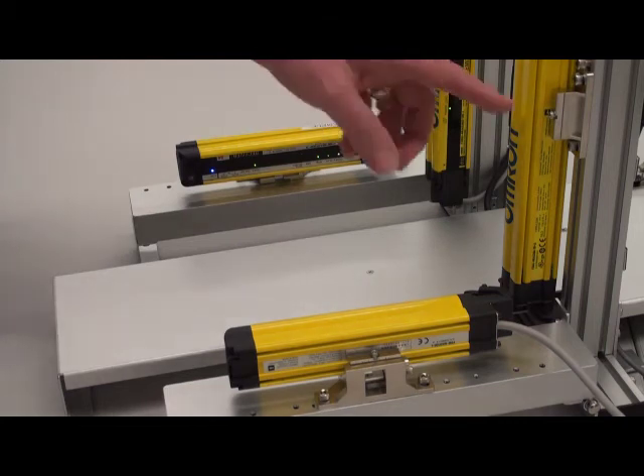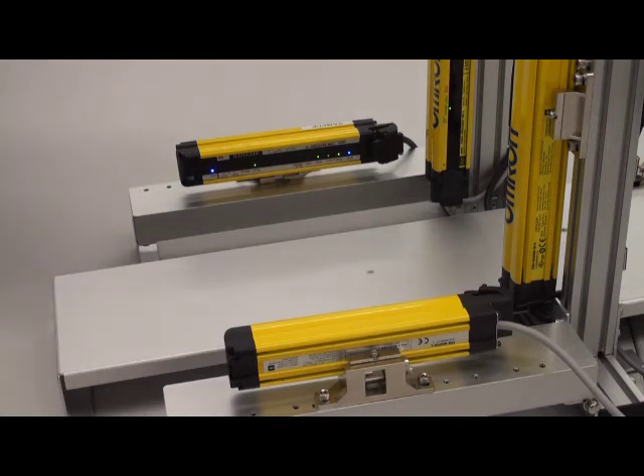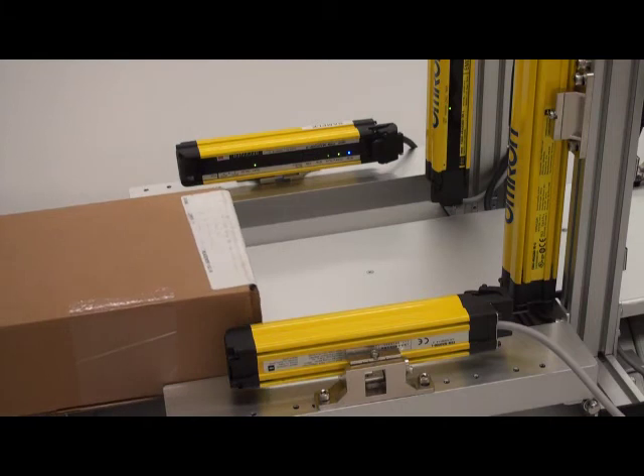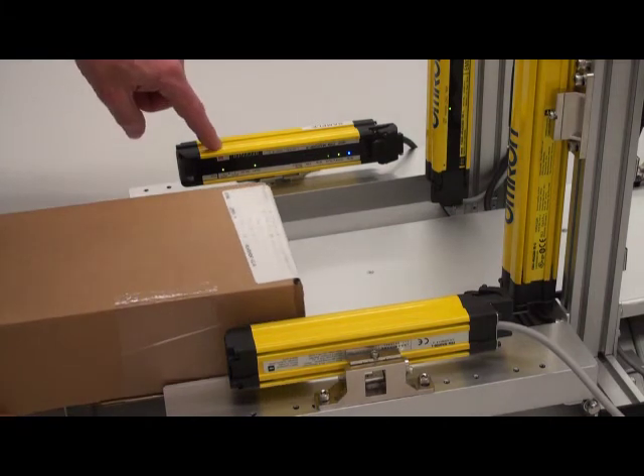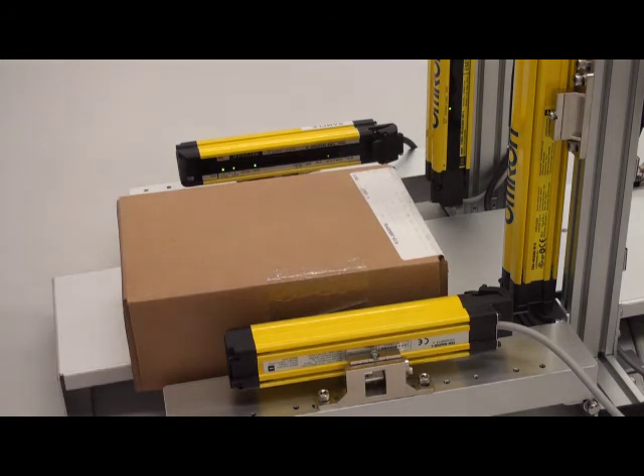And if it is, then you would just take a set screw and loosen it up and adjust it to make sure your indications are aligned. And now what I'm going to do is show you that when we do mute, you're going to have muting A illuminated. And then you're going to go to muting B. And now it's in the muting actuation phase.